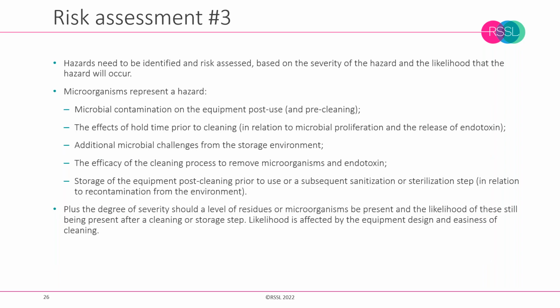So there are things that need to come into the risk assessment, and building on that microbial aspect, using the risk terminology of severity and likelihood is also quite useful in this situation. So the microbial hazards should be identified, and we should have an understanding of the likely types of microorganisms, and then consider their relative risk based on the severity and the likelihood that hazards can present themselves. So we need to be mindful of microbial contamination on the equipment post-use and pre-cleaning. We need to be mindful of the hold time prior to cleaning and the chance of microbial proliferation. And this also has association with the potential release of endotoxin.